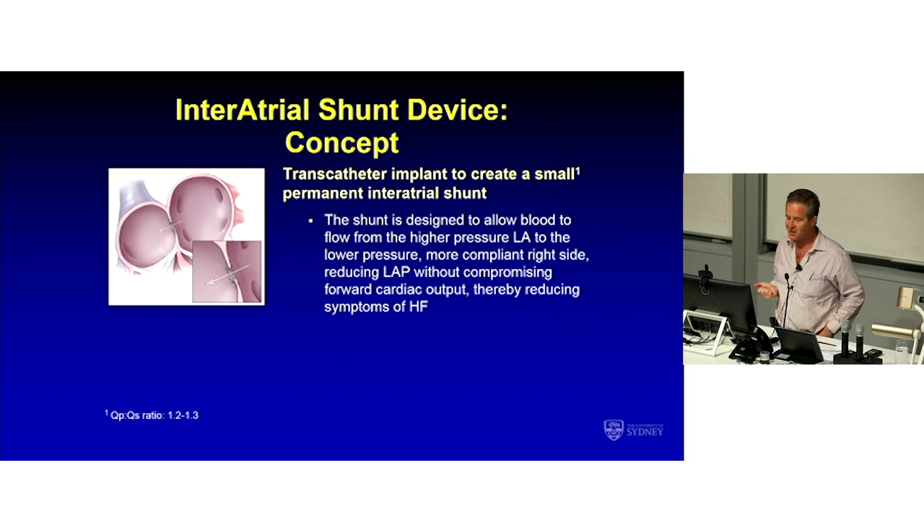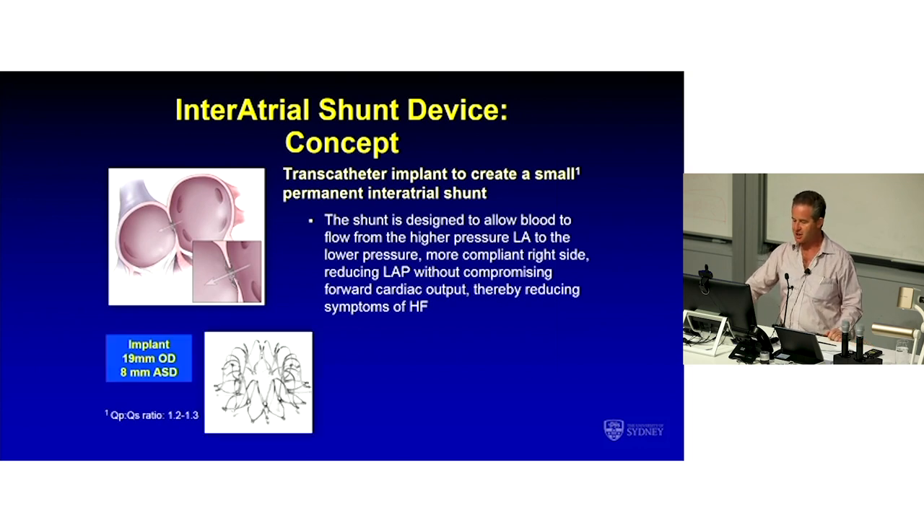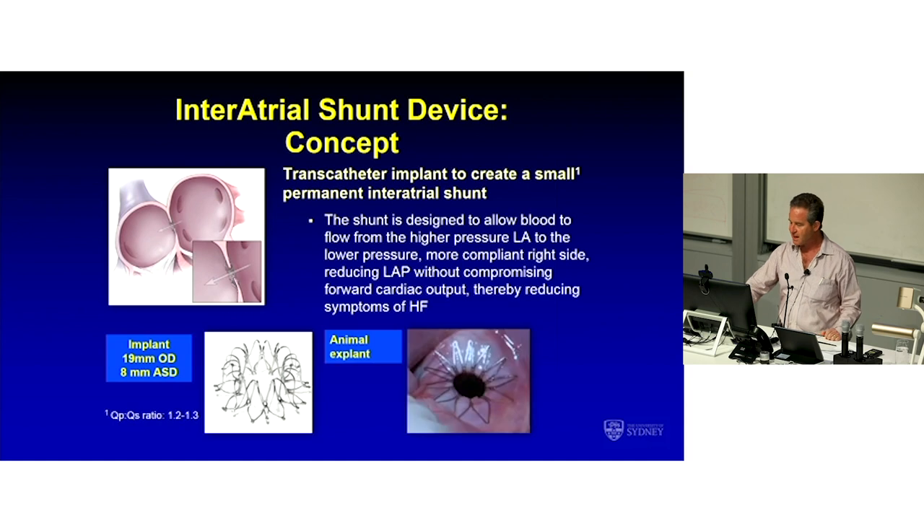You're trading an LA pressure problem for an RV volume problem, because there'll be more blood shunting left to right — but that RV volume problem is very well tolerated by the normal heart. We never close an ASD with a QP to QS of under 1.5 because the right ventricle can cope with that very easily. The aim of this device is to create a QP to QS of about 1.3, which goes up with exercise. The interatrial shunt device is a transcatheter implant — delivery time once into the femoral vein averages about seven minutes. That's what the device looks like, and that's what it looks like in one of the early iterations in an animal implant.